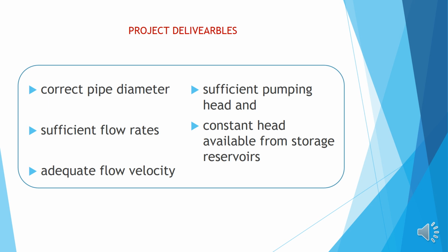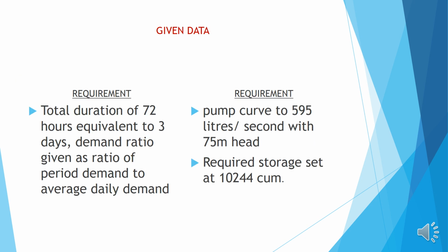The given data, the information that's known to us, is that the demand must be met continuously for 72 hours using a pump curve to supply at 595 liters per second with a given head of 75 meters. And the required storage for a bulk storage reservoir should hold 10,244 cubic meters.